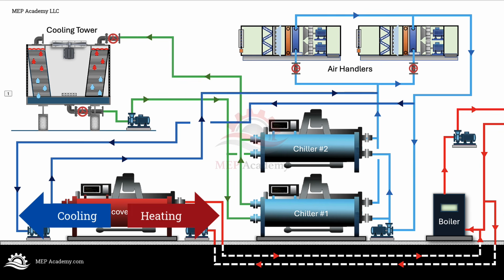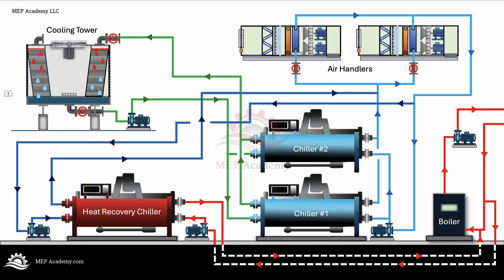This is why a heat recovery chiller should not always be judged the same way as a normal chiller. A standard chiller is usually judged by how efficiently it produces chilled water. But a heat recovery chiller may be producing chilled water and useful hot water at the same time. When both sides are doing useful work, the combined value of the machine can be much greater than looking at cooling alone. In simple terms, the building gets cooling from the evaporator side and heating from the condenser side from the same machine. That is the value of heat recovery.